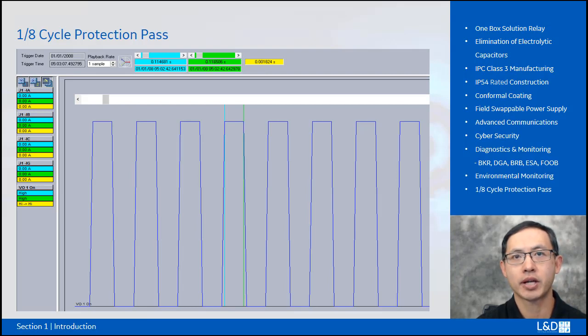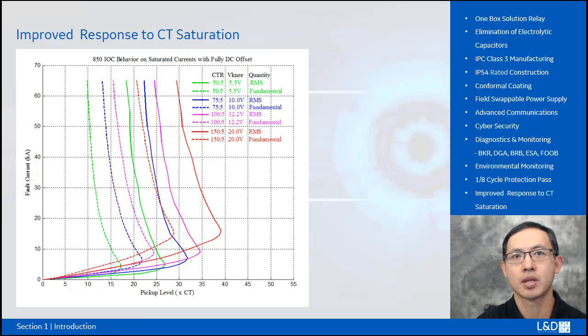1/8 cycle protection pass means that the relay is able to process information in about 2 milliseconds on a 60 Hz system, which enables faster trip time and less duration of the fault current. Improved response to CT saturation and other system transient conditions offer an option to operate IOC based on either the fundamental or from the RMS quantity.